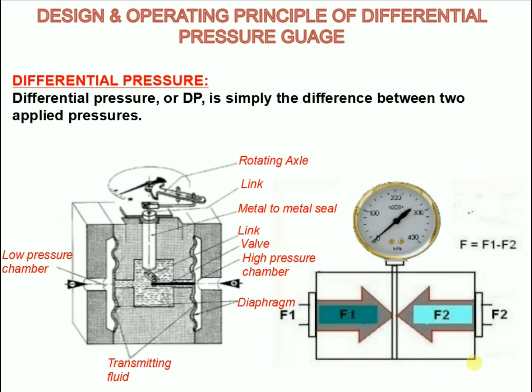Differential pressure gauges are used to measure the flow of a liquid inside a pipe. An orifice plate, venturi, or flow nozzle is often used to reduce the diameter inside a pipe. The differential pressure gauge measures the flow rate by finding the difference in pressure before and after the orifice. Differential pressure gauges are an easy way to get a visual indication of process flow.